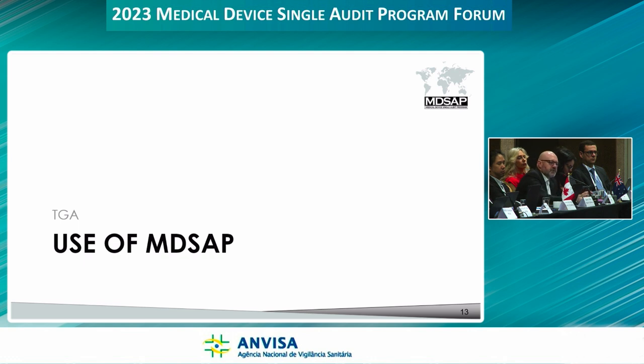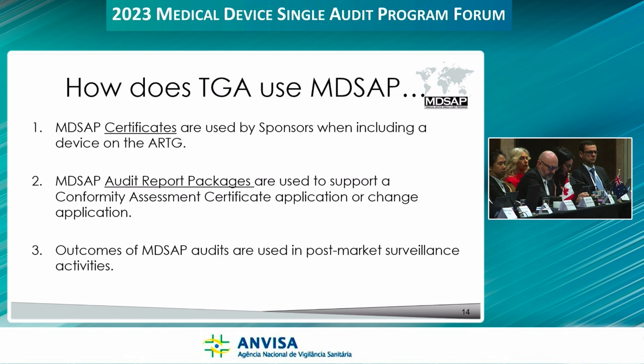Now I'm going to talk about how the TGA uses MDSAP. There are three main pathways. We utilise MDSAP certificates, which sponsors can use for ARTG inclusion. We also utilize the audit report packages and audit reports to support changes to a TGA issued conformity assessment certificate or for a new application. And we also utilize MDSAP in our post-market surveillance activities.